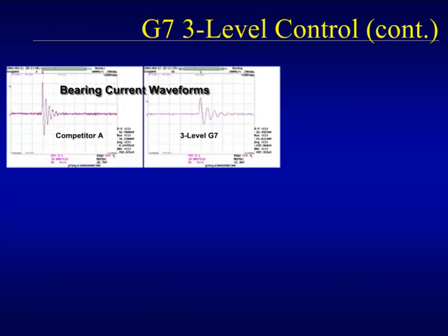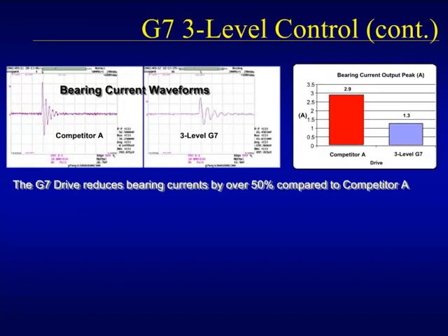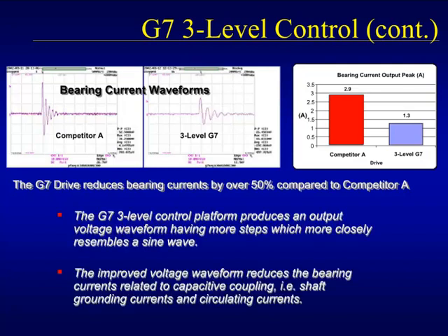Again, laboratory tests against a competitor's 2-level drive show that the G7 produces beneficial effects that are not possible with the standard 2-level drive. The tests show that the measured motor bearing currents are reduced by over 50% when compared with the competitor's 2-level drive. It is because of the G7's stepped output voltage waveform that the dVdt effects that contribute to common mode voltages are reduced and make the G7 the clear choice for increasing the life of a motor.